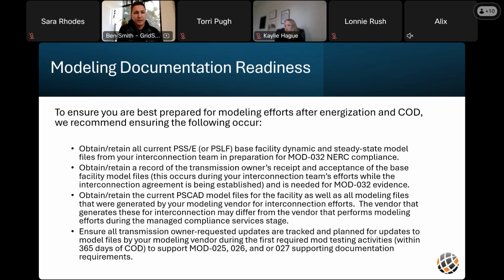I know John earlier today mentioned some modeling documentation readiness, and Kaylie just mentioned this on her prior set of slides, but one thing we validate for generator owners or compliance is the Mod 32 standard, and that's simply a collection of the base facility model files and the transmission owner's receipt and acceptance of those files. That occurs during the interconnection process, but sometimes there are different teams your company might work with for asset management versus the interconnection team, and there might be a delay of a year or two from when the interconnection agreement is established to when you're facing NERC compliance. So we often chase that down with a bit of a disconnect of where that documentation was housed.